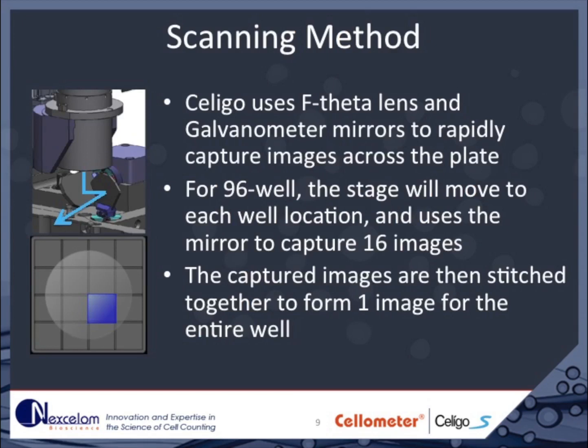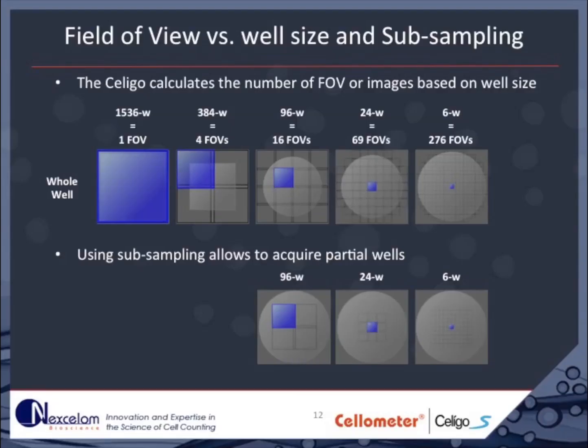The Celigo is not a typical microscope objective-based instrument. Instead, the optical system allows for acquiring multiple images based on a single focus event. Each well of a 96-well plate is covered with 16 images that are automatically stitched together. In the Celigo software, a single image is called a field of view. Different size wells require different numbers of fields of view to cover the entire bottom of the well. A 1536 well requires a single image, whereas a 6-well plate requires 276 images. If appropriate for your assay, a smaller number of images per well can be acquired.